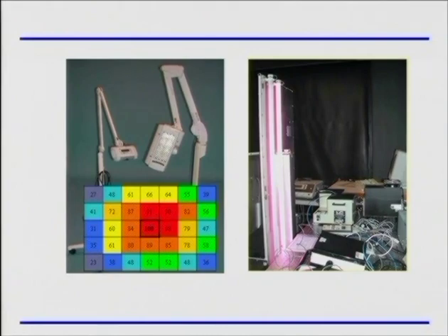So this is what we found with this device. Just normalizing to 100 in the middle. You can see we've kind of color-coded to make it a little bit easy. You've got to be careful how big a lesion you're going to treat with this device now, because the light is definitely dropping off 1 centimeter, 2 centimeters away. And you can't tell with the human eye. But if you make this measurement, you can begin to put restrictions on the size of lesion that you can treat. Or say, if you're treating with a large lesion, you have to treat a little bit longer, because out at the edges, they're not getting as much light as they are in the center.